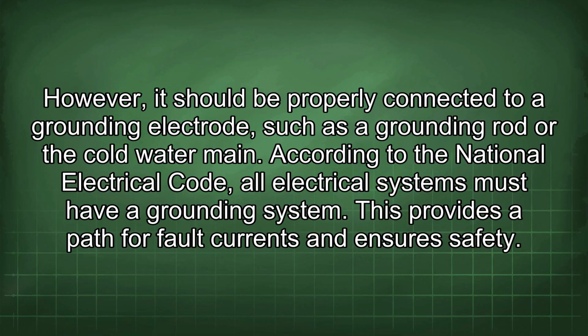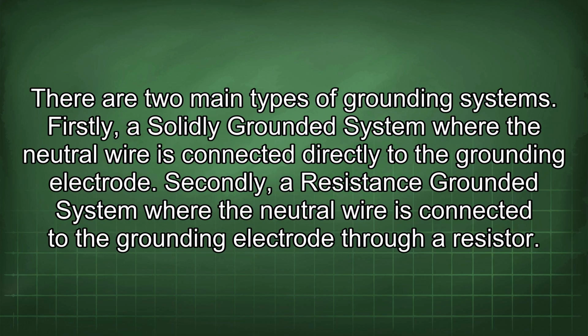According to the National Electrical Code, all electrical systems must have a grounding system. This provides a path for fault current and ensures safety. There are two main types of grounding systems. Firstly, a solidly grounded system where the neutral wire is connected directly to the grounding electrode. Secondly, a resistance grounded system where the neutral wire is connected to the grounding electrode through a resistor.